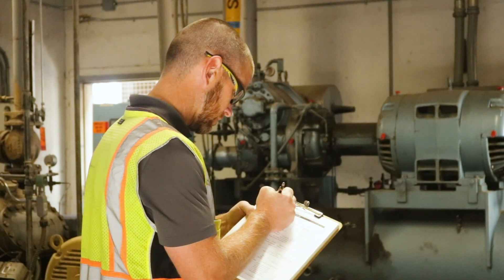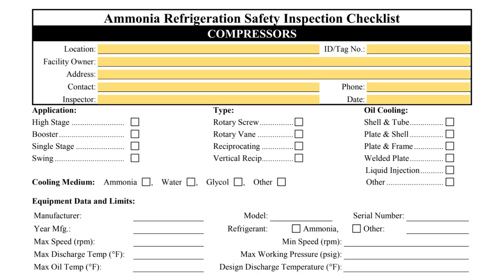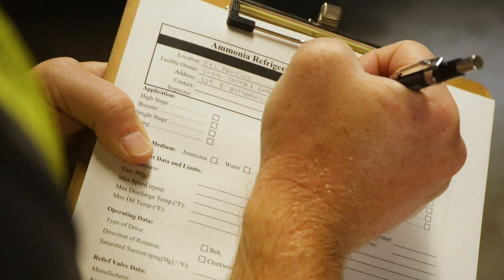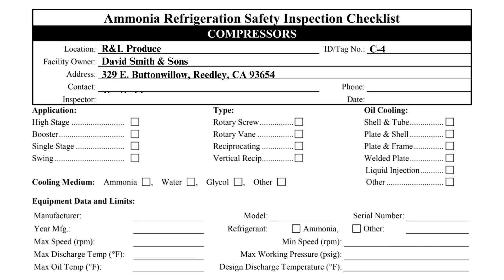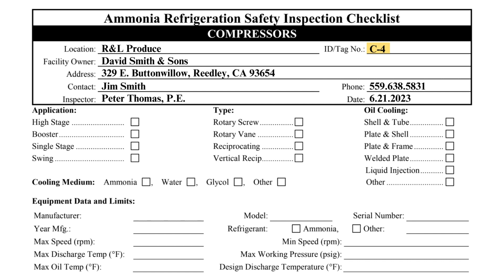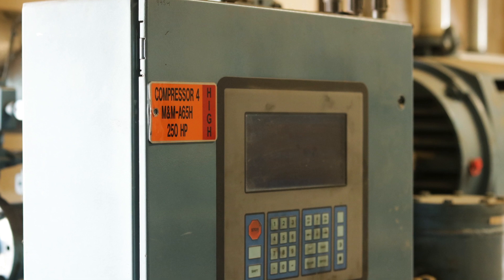The simplest part of completing a compressor checklist is filling out the contact information. Each IIAR 6 checklist requires the inspector to indicate the location, owner, and physical address of the system. The contact's name and phone number should be the facility representative responsible for ensuring the inspection is completed. Additionally, the inspector must write his or her own name and the date of the inspection. The ID or tag number belongs in the upper right corner and can typically be found on the equipment label or P&ID.